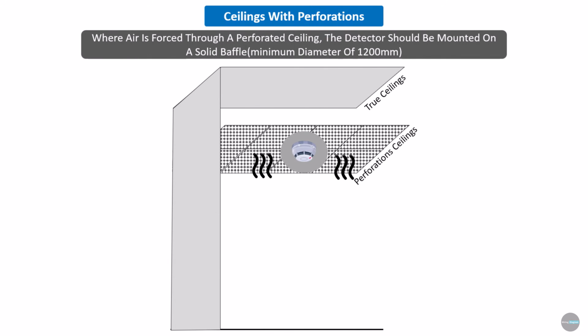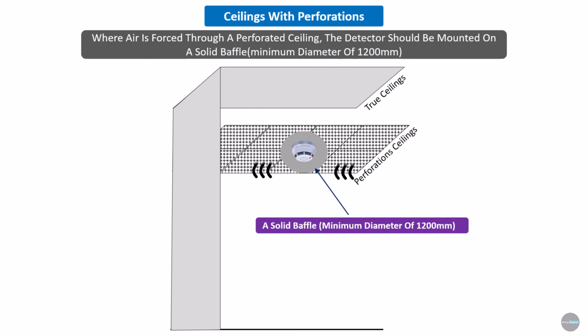If there is high airflow beneath a perforated ceiling, the detector should be installed below the ceiling with a solid baffle of at least 1,200 millimeters diameter around it. This helps prevent the airflow from affecting the detector's performance and ensures proper smoke detection.